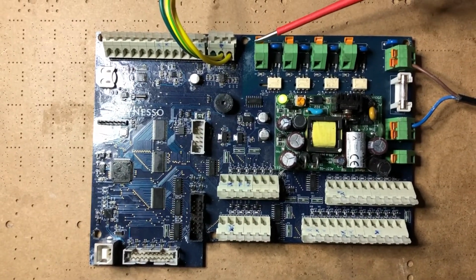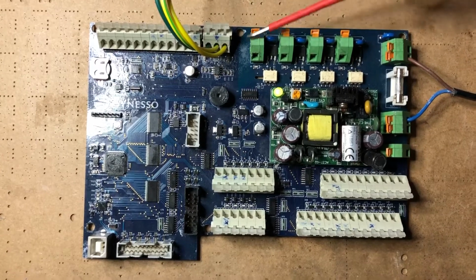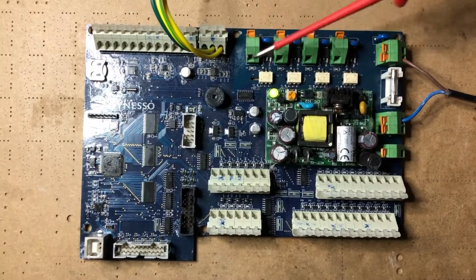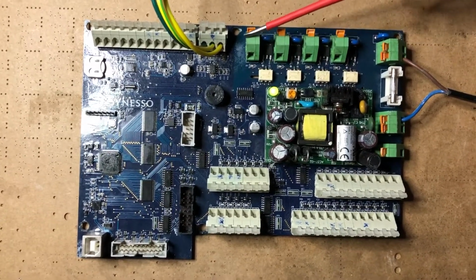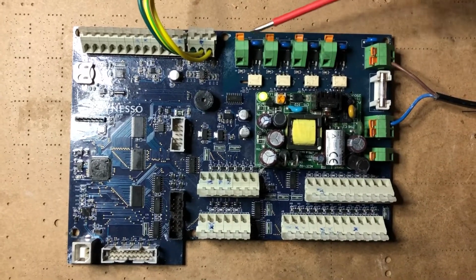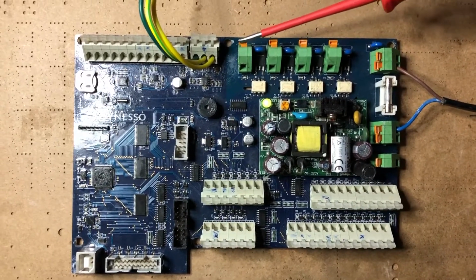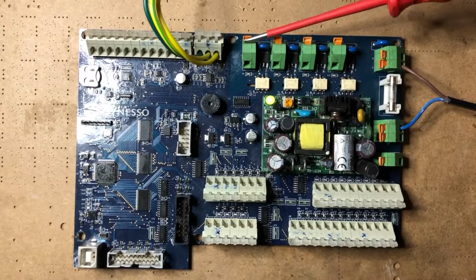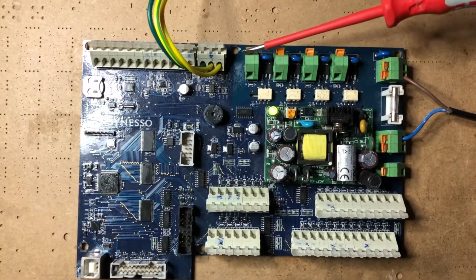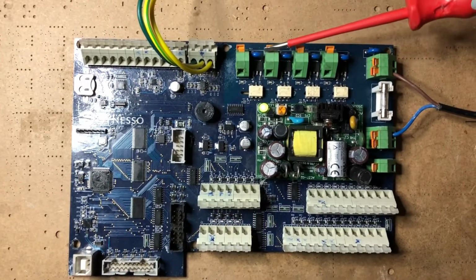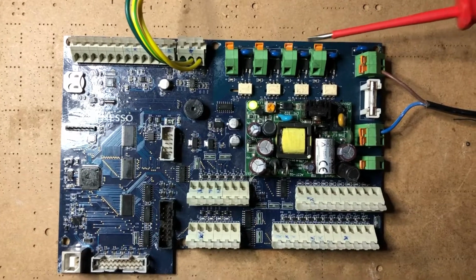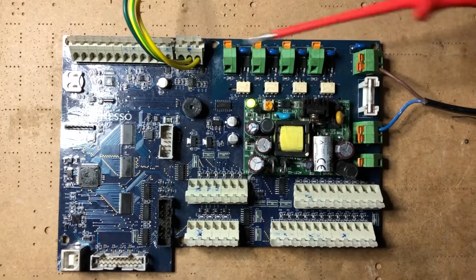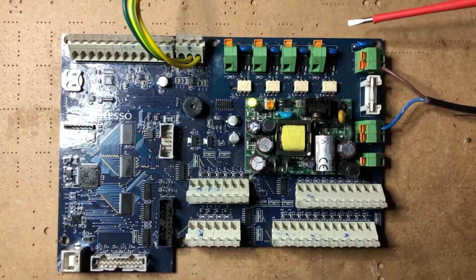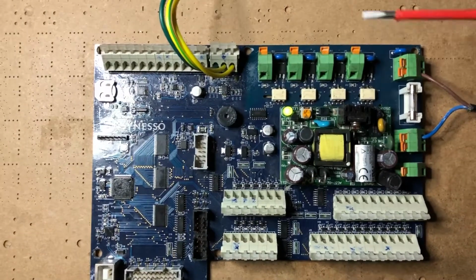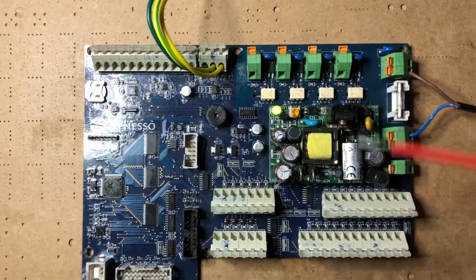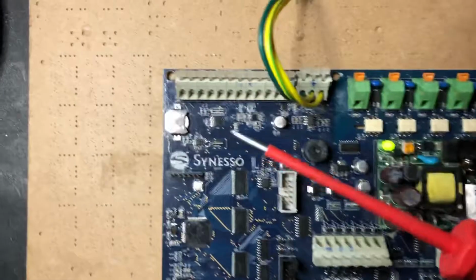So let's say you've lost pump 1 - you've blown this to the crap. We can repair it actually - if you send us back the board, we'll repair this circuitry for you. But if you're in a pinch and need to get the customer going again, you can simply transfer pump 1 to pump 2, pump 2 to pump 3, pump 3 to pump 4. Just switch your outputs along left to right, then bear in mind you have to swap all the other electronics to match.